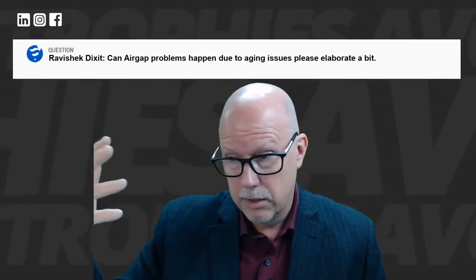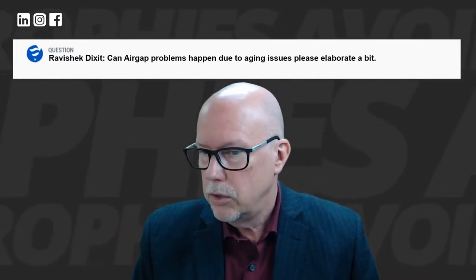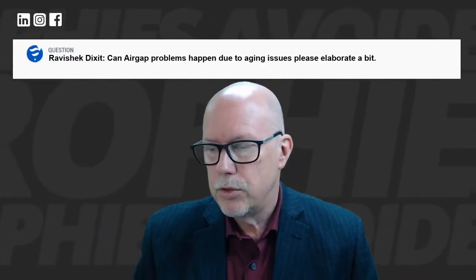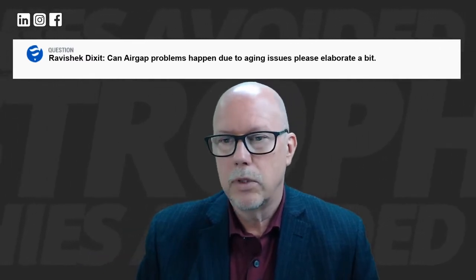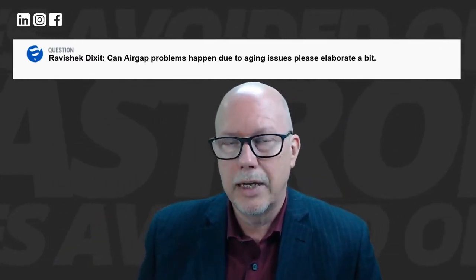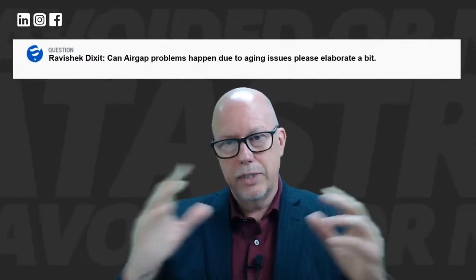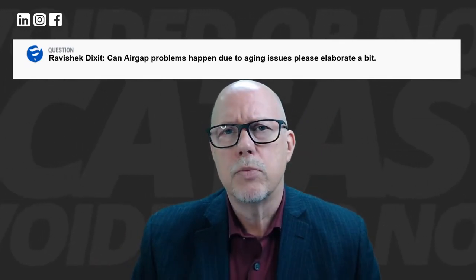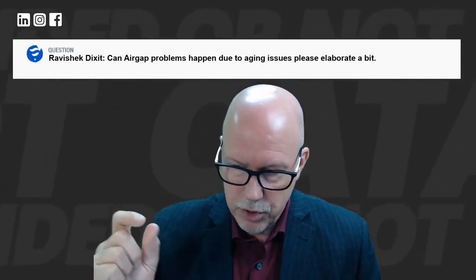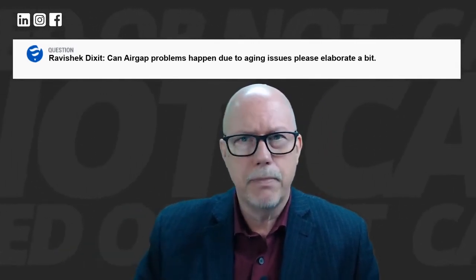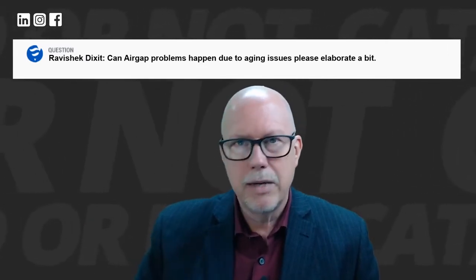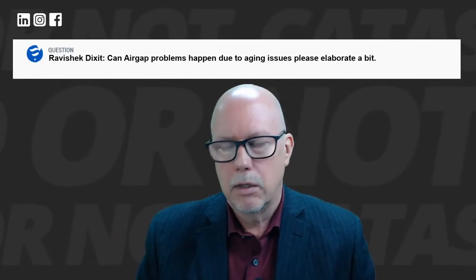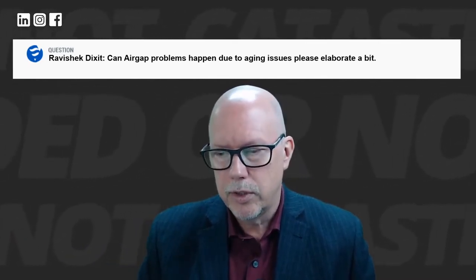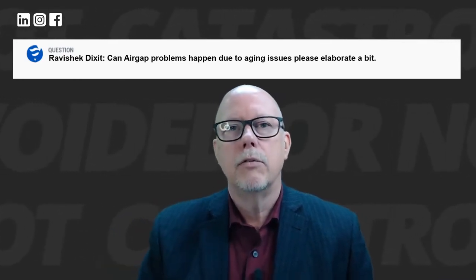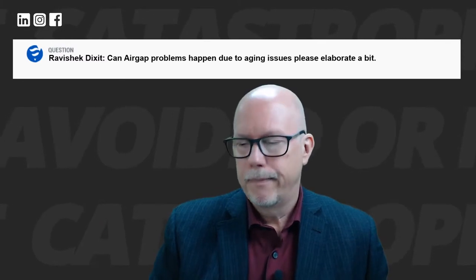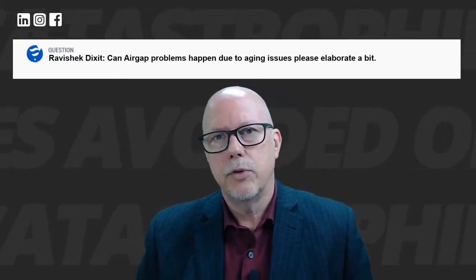If they fix it, it's not an error to fix it, but it wasn't required to protect the unit. We have quite a few older units where the tolerances we apply are based on the age of the unit. Very old units have very thick steel, everything is over-designed and over-manufactured, so you can get away with much more than today. Today, a small issue with stator shape, stator expansion, rotor shape, or shaft vibration can quickly become critical and cause damage to new units, because they're at the limit of what's required to function properly. So we're much more stringent on results for new units than for old units.